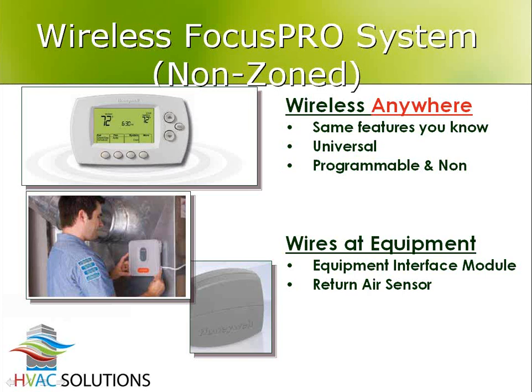This shows you some basic pieces of a non-zone system. We'll talk about zoning in a minute, but with a non-zone system, you have more pieces than normal. Normally you just have a thermostat on a regular job, right? But with the wireless, I've got to have a thermostat. And since it's wireless, my furnace isn't wireless, so something has to tell the furnace when to go on. The furnace needs wires to be told when to go on and off. So this thermostat talks wirelessly to an equipment interface module, or EIM, and that equipment module, as you can see in this picture here, is physically wired over to the furnace. So it's not 100% wireless, it's just wireless throughout the home. But at some point, even if it's just for 2 or 3 feet, you're going to have wires going from the controller over to the actual furnace or boiler or whatever it is you're trying to wire up to.